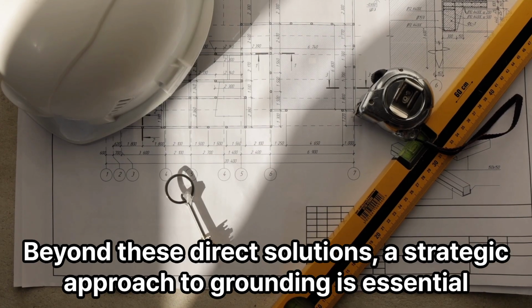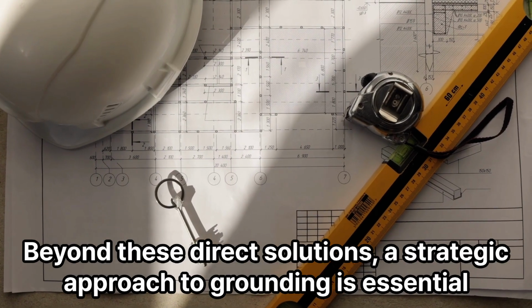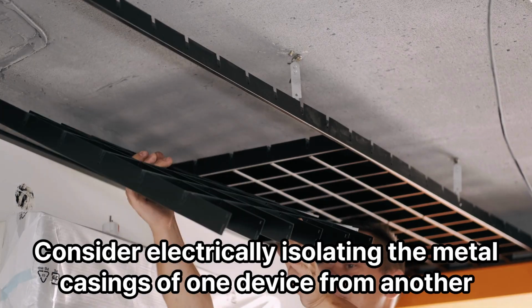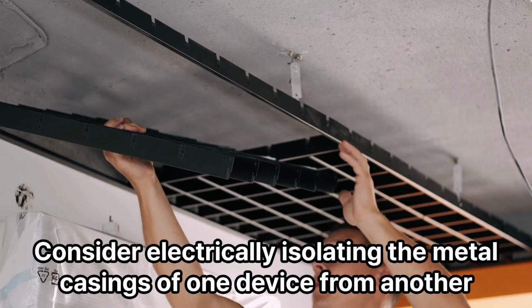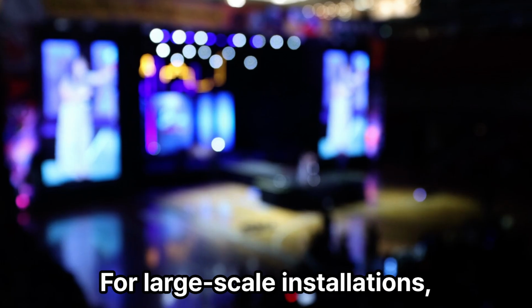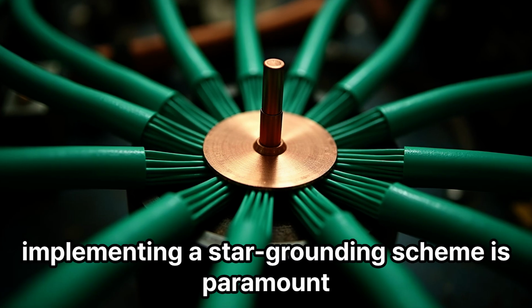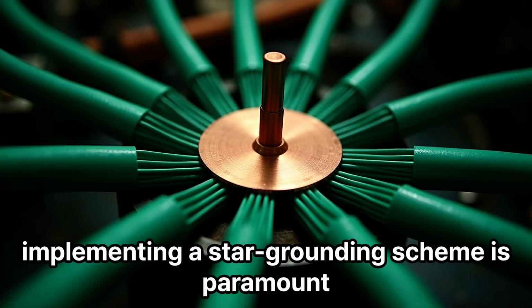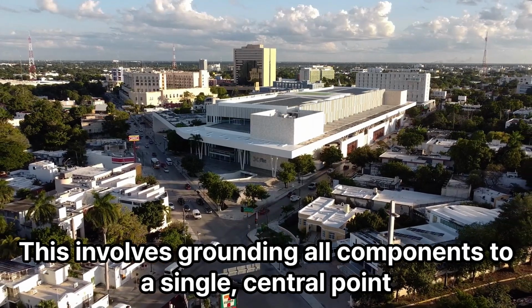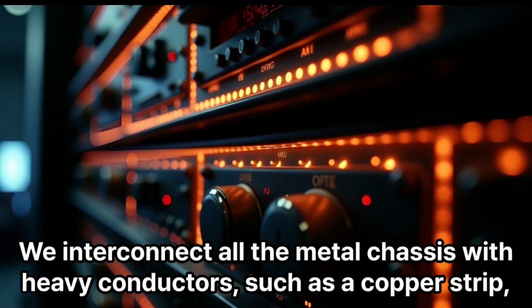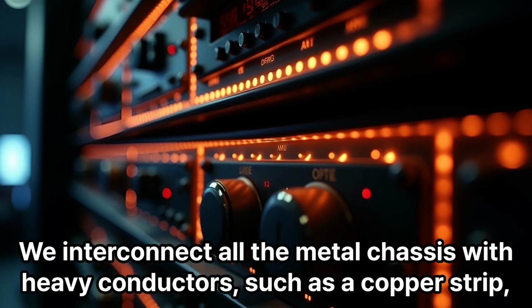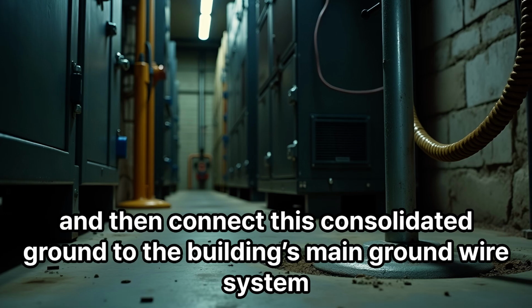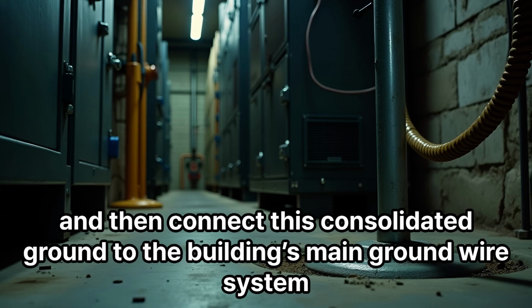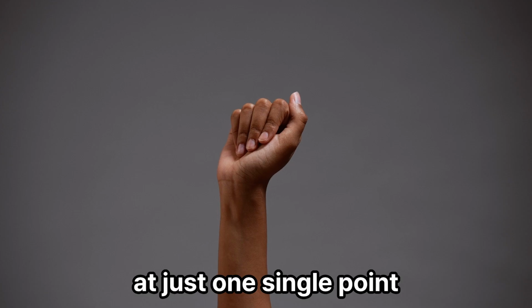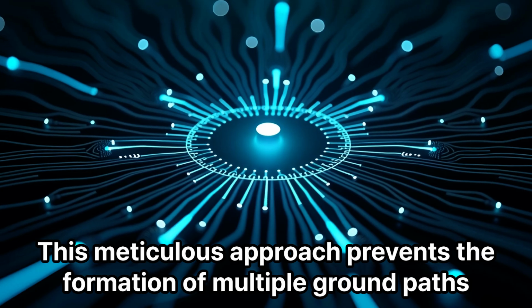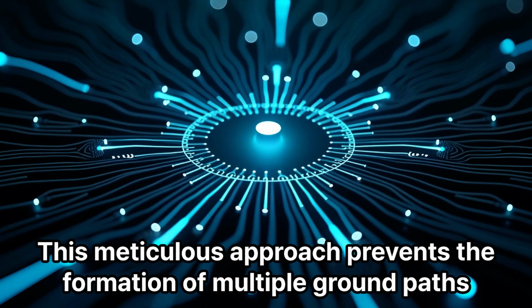Beyond these direct solutions, a strategic approach to grounding is essential. Consider electrically isolating the metal casings of one device from another to eliminate the loop. For large-scale installations, implementing a star grounding scheme is paramount. This involves grounding all components to a single, central point. We interconnect all the metal chassis with heavy conductors, such as a copper strip, and then connect this consolidated ground to the building's main ground wire system at just one single point. This meticulous approach prevents the formation of multiple ground paths.